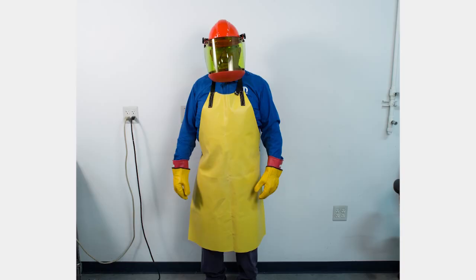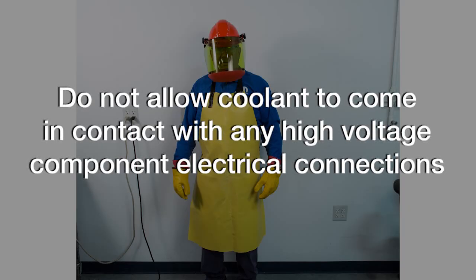Be sure to use the proper safety equipment when working on any high voltage system or component. Failure to do so may result in serious or fatal injury. Caution: do not allow coolant to come in contact with any high voltage component electrical connections. Engine coolant will create a conductive path and cannot be effectively removed, resulting in a loss of isolation and replacement of the contaminated high voltage component.